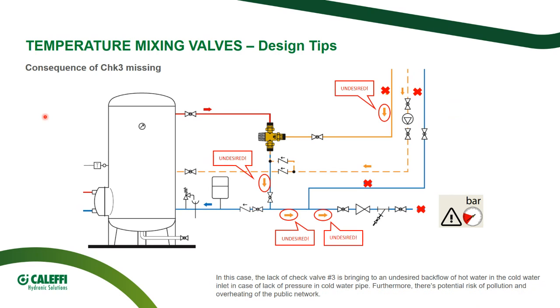So let's finish the scenario. Let's forget check valve number 3. Check valve number 3 is protecting the cold water inlet of the valve. If I forgot it, I might have injection of recirculated water within the cold water line, backwards up to the main distribution line. So I might also have potential pollution to the municipal network or to the building network or to the main line.